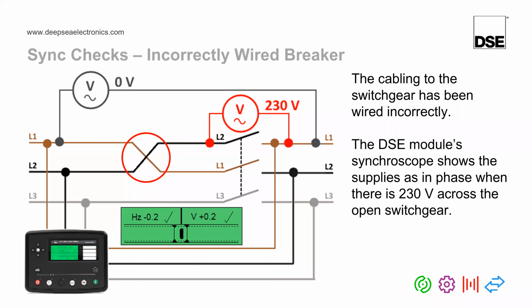Some people say that they don't have to do these checks because they wire directly on the lugs of the breaker themselves, so it's much more safe and secure. Unfortunately, that is not always true, because if you have a cross here and also have a cross on the sensing wires, you could come across the same problem. So regardless of how you wire your sensing on the breakers further downstream, it does not matter. You should always do this phase rotation check across the breaker using a multimeter across the open breaker, doing L1, L2, and L3.